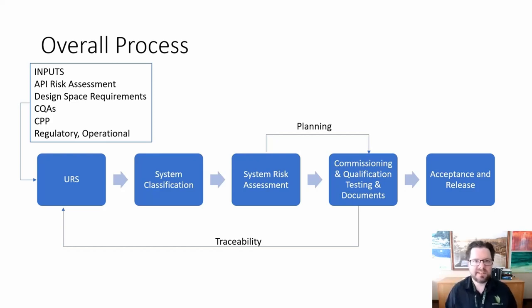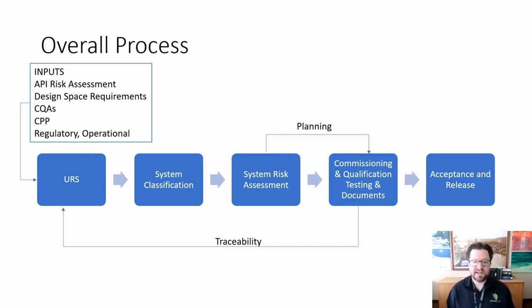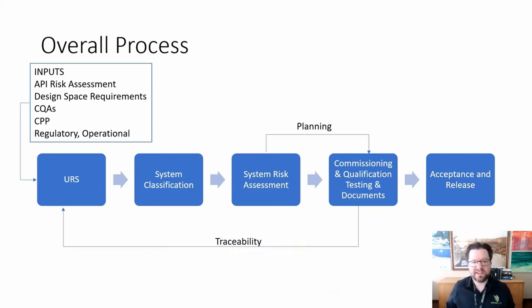The third thing is really the system risk assessment that you need to do. The ICH has produced wonderful documentation on how to conduct that, not only in the development process — the Q8 — but also in the Q9, which is the risk assessment, and also in the Q7. You should take a look at those documents and really run a risk assessment that will provide a scientific rationale for your URS and also for your system classification. And then obviously your commissioning, qualification, and testing document — these are the four key things that you need to do in order to select the right equipment. If you do this, you'll have traceability of your commissioning documents back to your URS, which is the key thing.